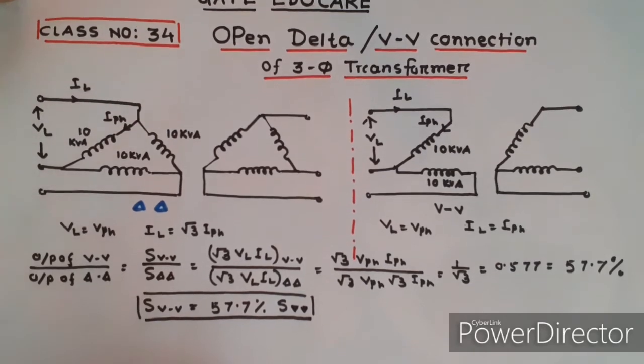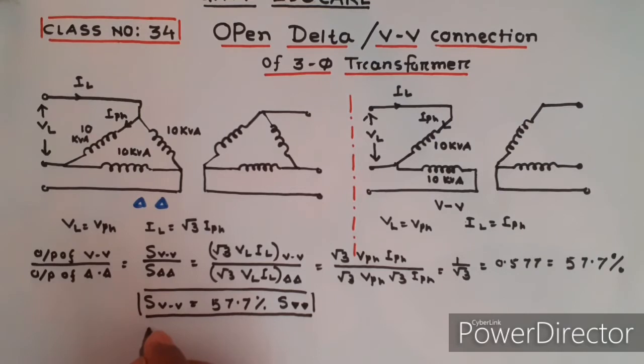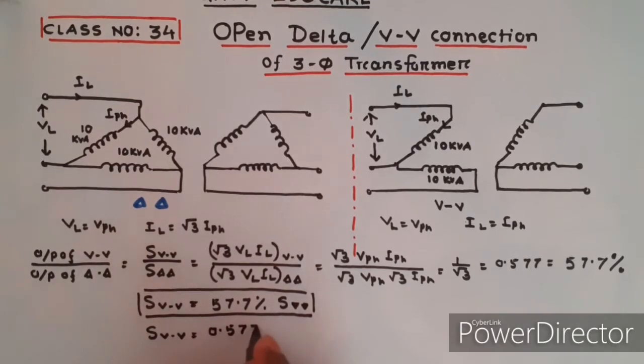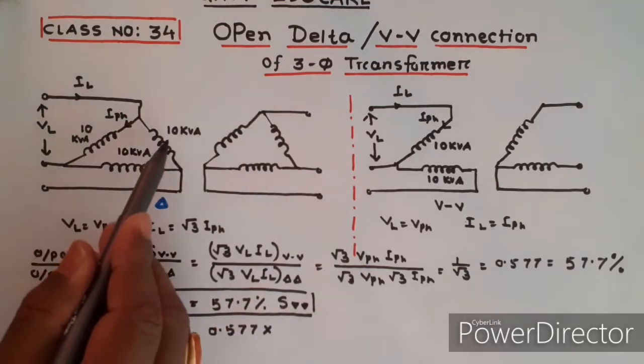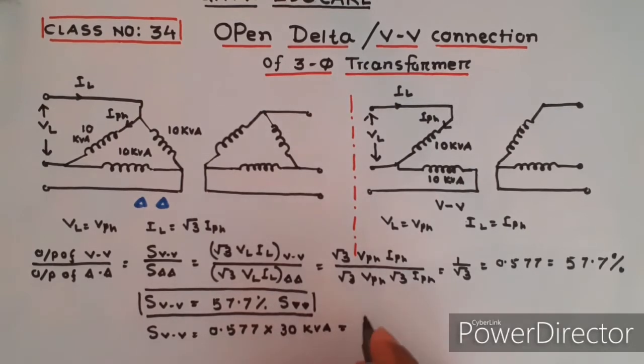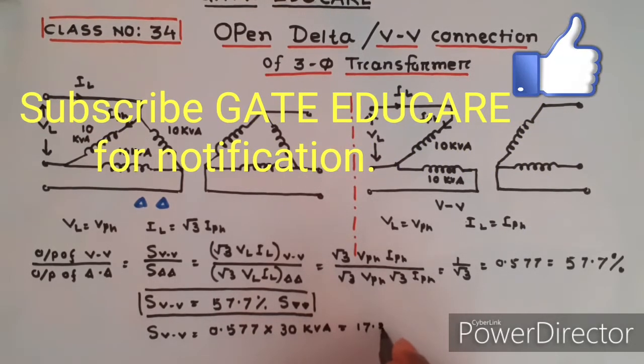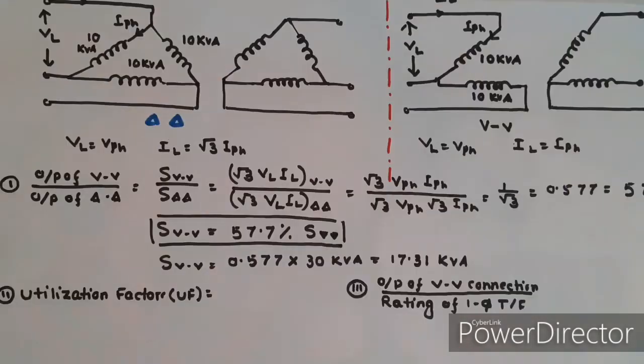Therefore, the output of the V-V connection equals 0.577 times the total output of the delta-delta connection. The total delta-delta output was 10 + 10 + 10 = 30 kVA, so the V-V output becomes 0.577 times 30 kVA, which equals 17.31 kVA.